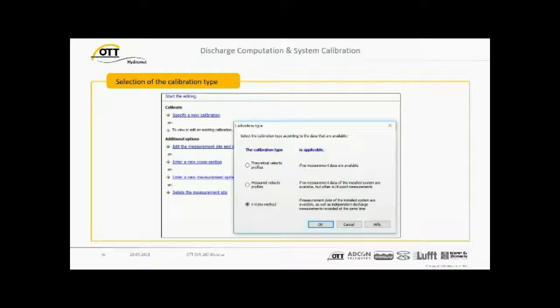So you go to the field at different flow situations, you do a comparing measurement, and you enter into ProDis the date and the start time of your measurement and the stop time, and the result, what you have measured, the Q in cubic meters per second, and the water level. You also enter the sensor data from the SVR 100 for the same time period. What ProDis is doing in the background is the index method. It computes the real existing mean velocity of the section from your comparing measurement and relates this to the velocity of the surface velocity radar.